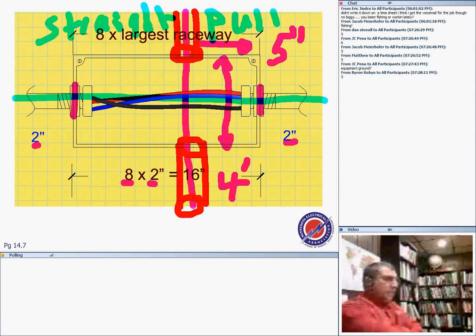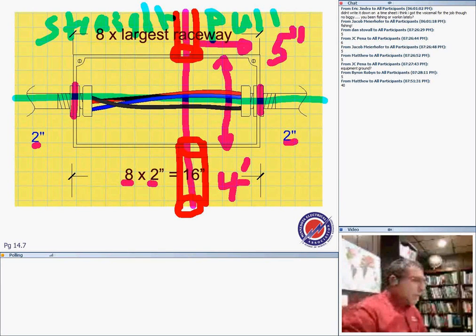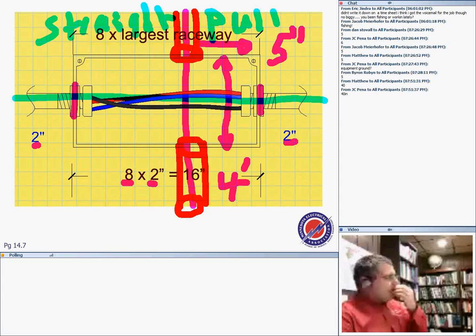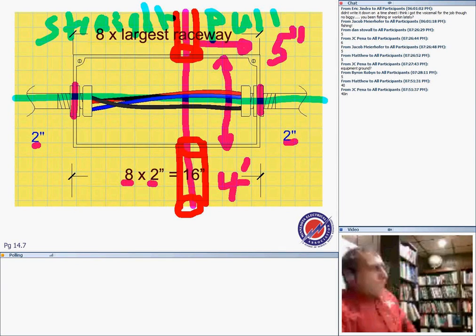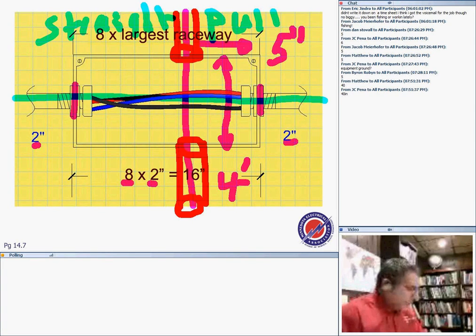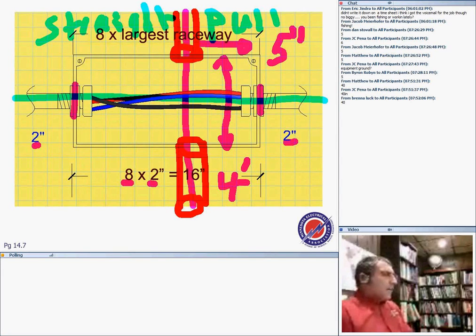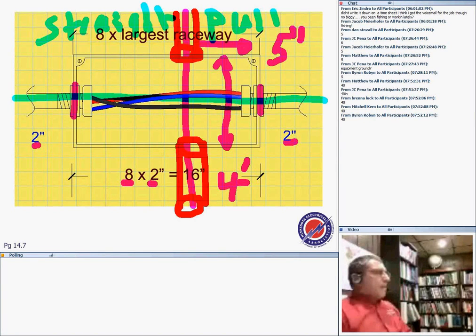To give you a hint, it's a straight pull, and the rule of a straight pull is right in front of you. Based on this, what would be the height? I need a couple more. What's the height? Look at that. I'm coming from one wall, exiting the opposite wall. That's called a straight pull. In 314.28, if you have a straight pull, it's 8 times the largest conduit engaged in the straight pull. So the options, guys, are 8 times the largest conduit coming from the top or leaving from the bottom. Which one is the largest? The top. So that would be 8 in this case.